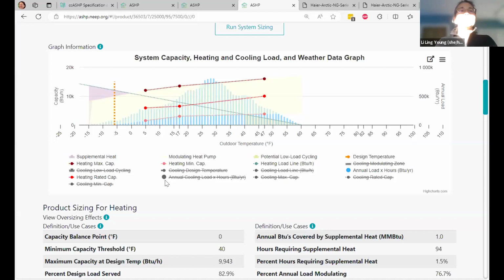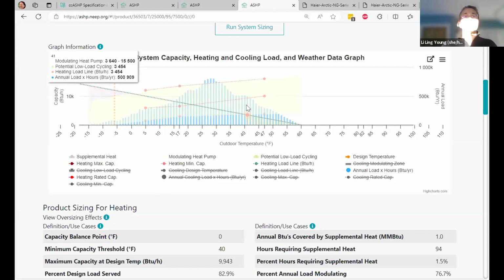But what I want to say about this heat pump is sometimes it actually makes sense to undersize a heat pump, even though you might end up with the need for a little bit of supplemental heat. The reason to do that is this section right here - you get much better performance at the part of the season when you're going to be consuming a lot of energy. You get much better efficiency here. And that would be a reason to undersize.